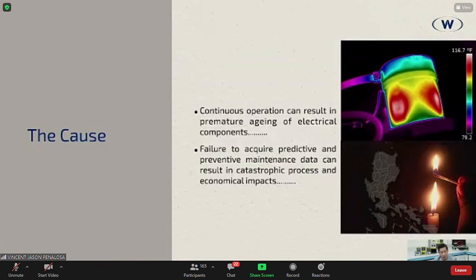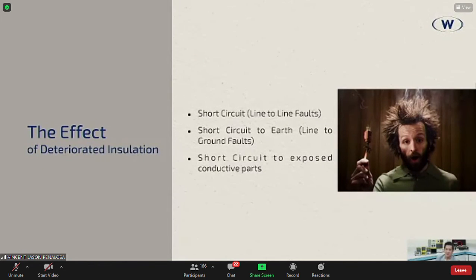No? Now, if you go to hospitals, how much trouble do you think if your power supply in your operating theater, regardless whether you had the UPS and redundancy of a generator, if your system shuts down while someone is on the operating table? No? What is it going to cost you if one of the medical practitioners actually gets hurt because of electrocution? Or worse, the patient. Diba? So all these things we need to consider whenever we're designing or maintaining our power system, especially for critical care units for hospitals. Now, what are the effects of deteriorated insulation?